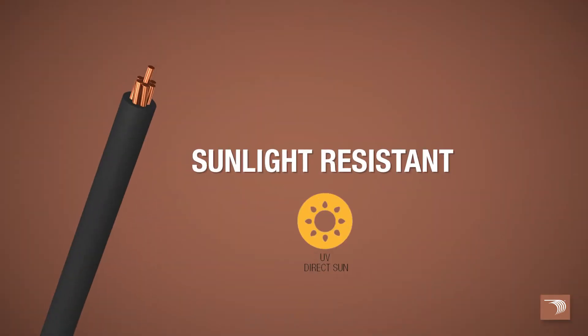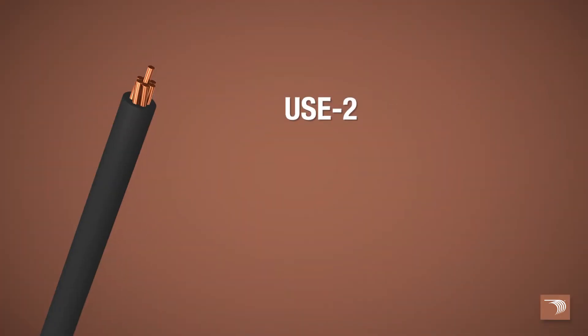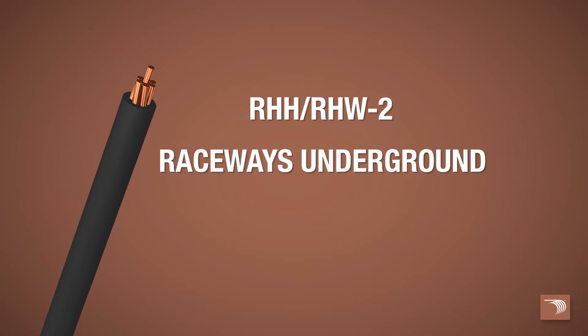Our Type USE-2 is sunlight resistant in all colors, sizes 10 gauge and larger. It's permitted for applications requiring direct burial per UL854. USE-2 is primarily used as a direct burial conductor, whereas the RHH-RHW-2 is used in raceways underground.